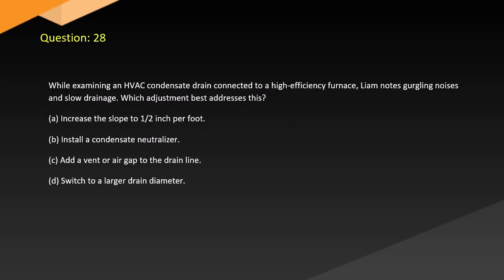Question 28. While examining an HVAC condensate drain connected to a high-efficiency furnace, Liam notes gurgling noises and slow drainage. Which adjustment best addresses this? A. Increase the slope to 1/2 inch per foot. B. Install a condensate neutralizer. C. Add a vent or air gap to the drain line. D. Switch to a larger drain diameter.